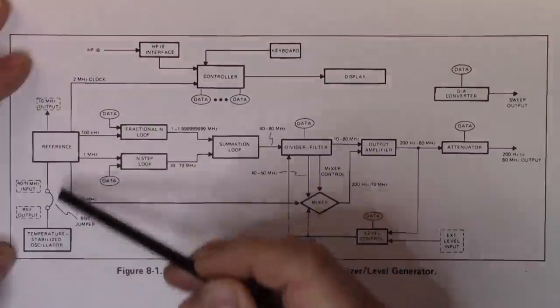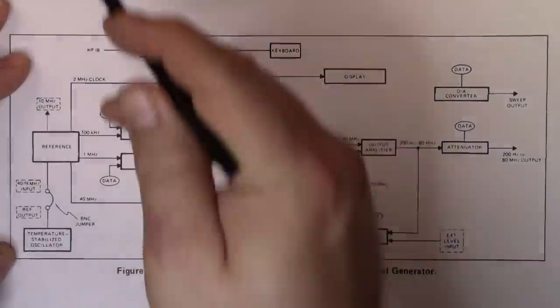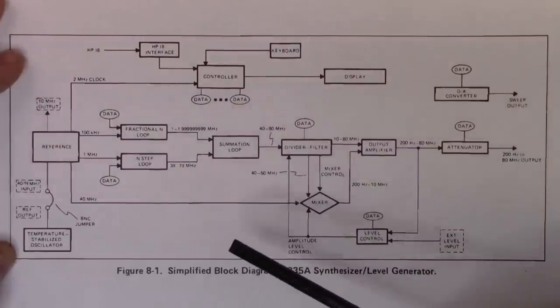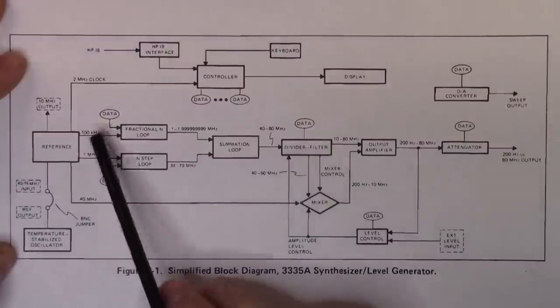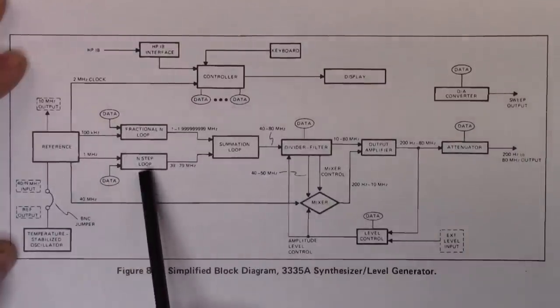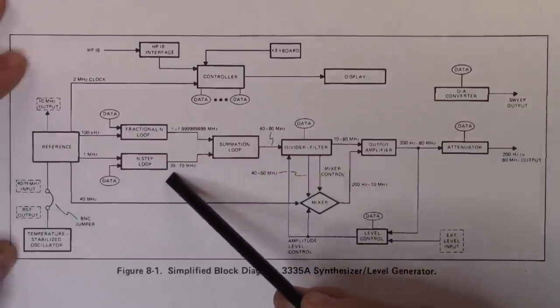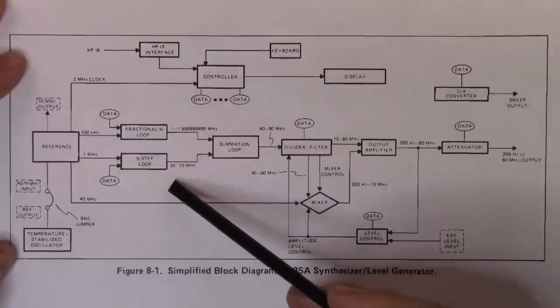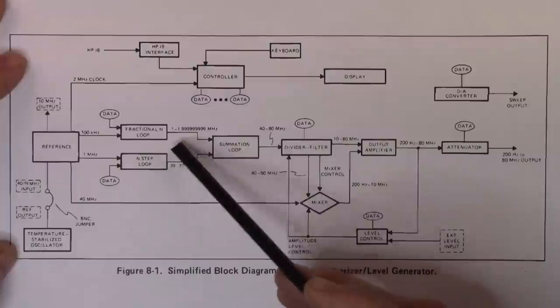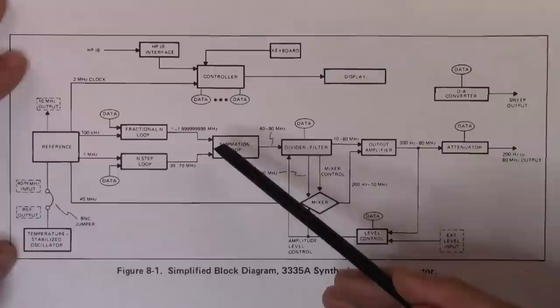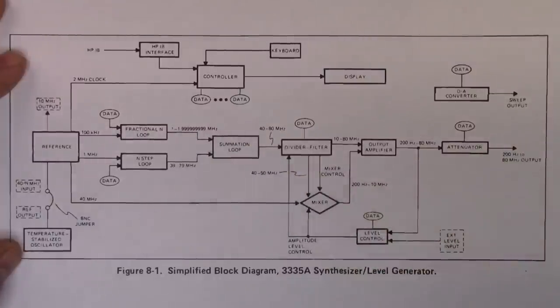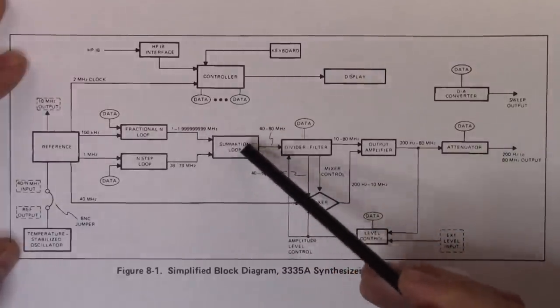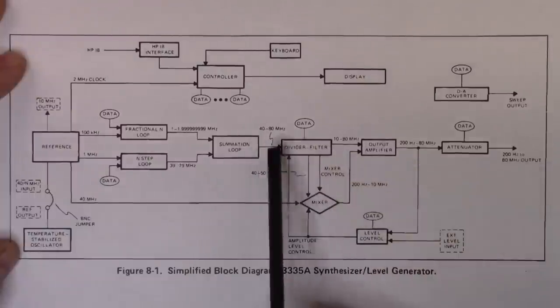And it comes out and goes through a BNC jumper into a reference signal input to the internal reference. And so these two items are phase locked together. And this then puts a 10 meg out that you could go use on other units. And then that reference sends out 1 meg and 100 kilohertz. And the one megahertz goes into an N step loop. And that will give us frequencies ranging from 39 to 79 megahertz. And then the 100 kilohertz goes into a fractional N loop which will give us frequencies from one to basically two megahertz.